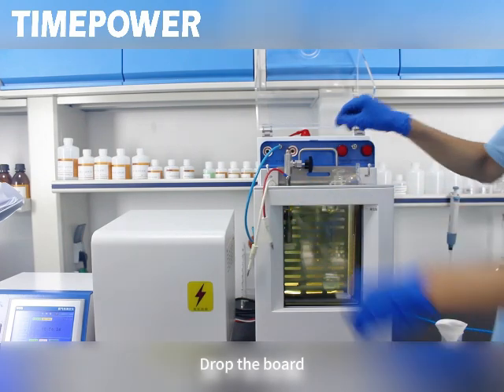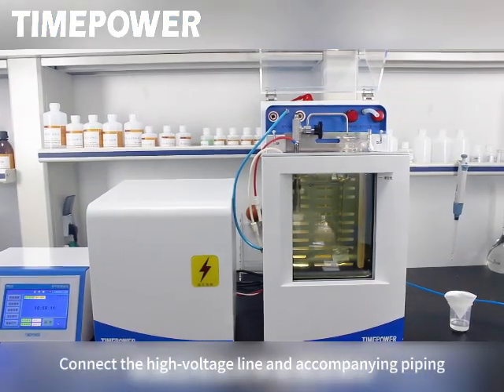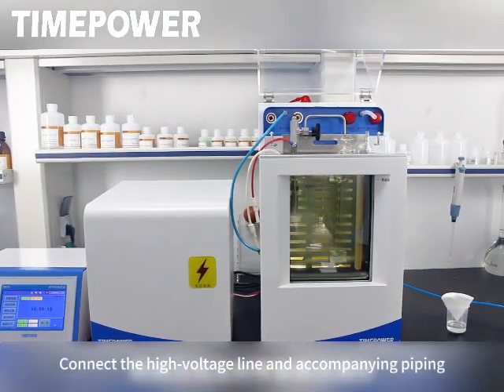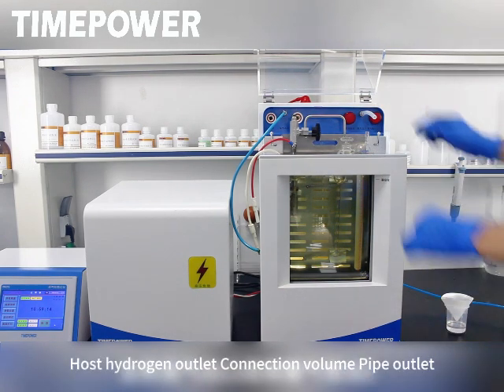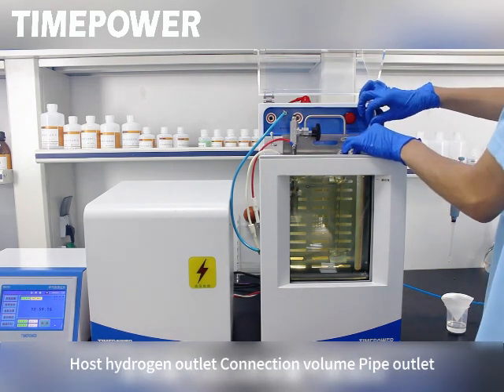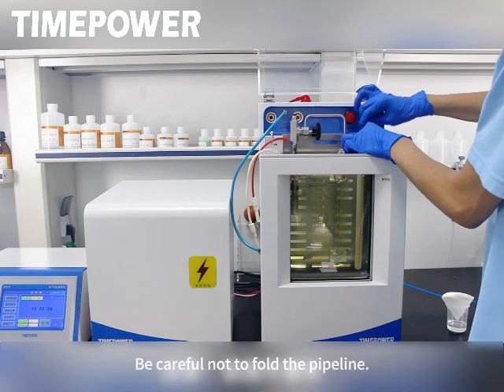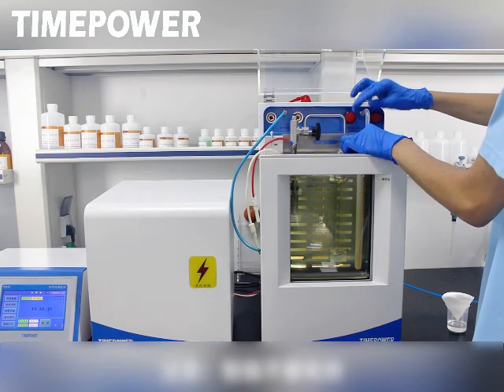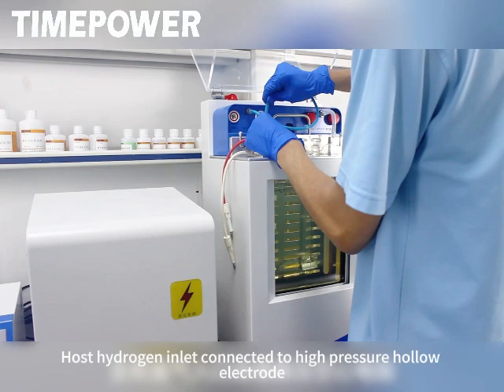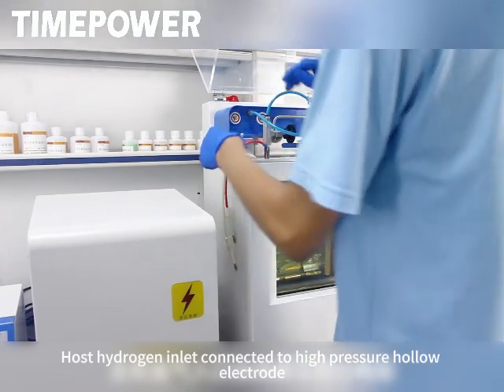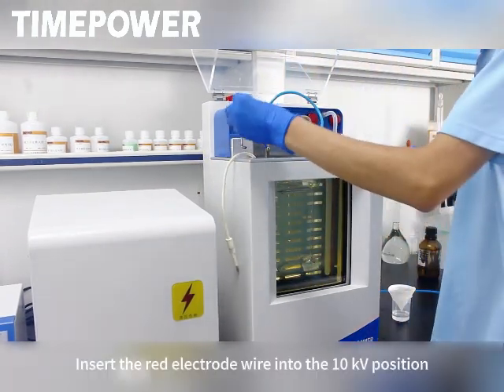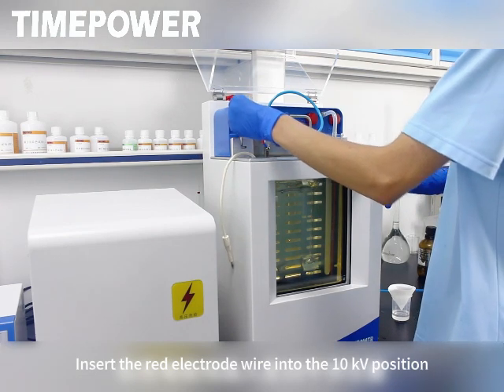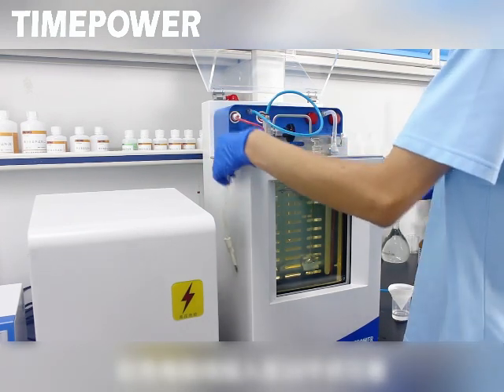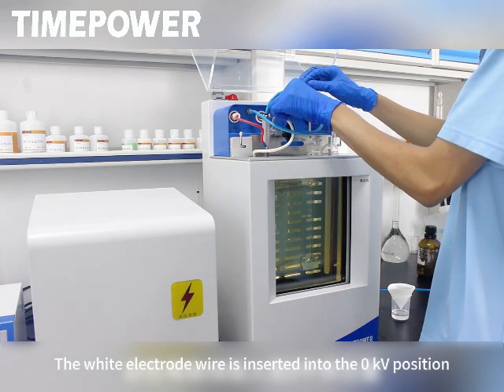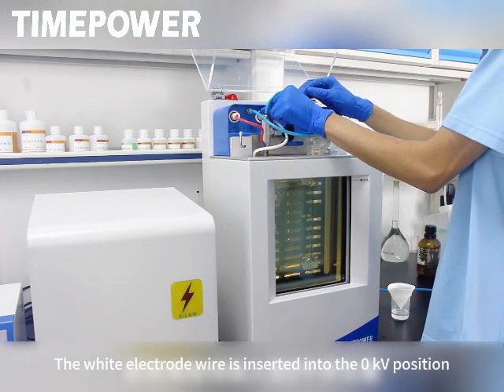Drop the board. Connect the high voltage line and accompanying piping. Connect the host hydrogen outlet to the volume pipe outlet. Be careful not to fold the pipeline. Connect the host hydrogen inlet to the high-pressure hollow electrode. Insert the red electrode wire into the 10 position. The white electrode wire is inserted into the 0 position.